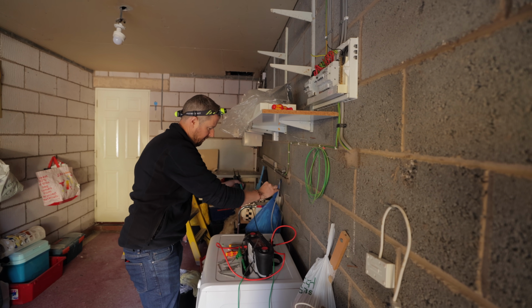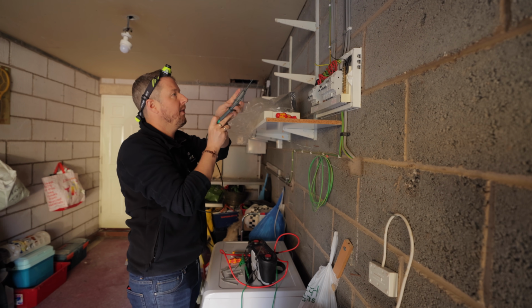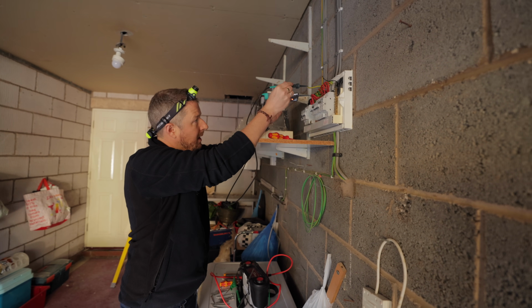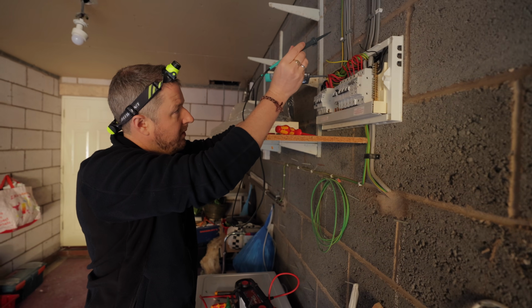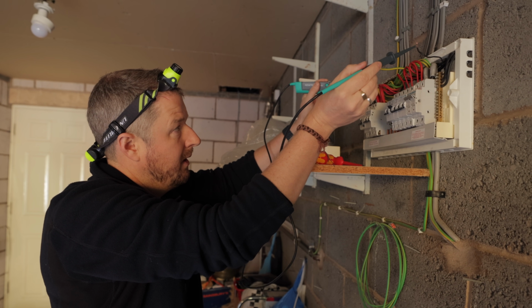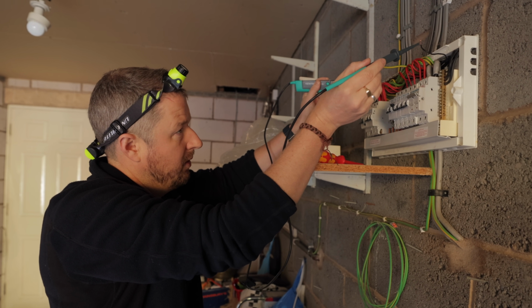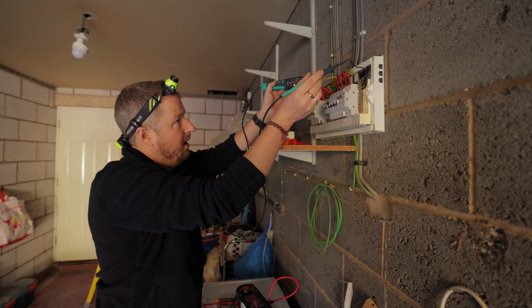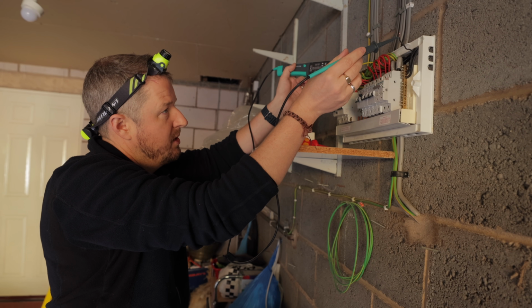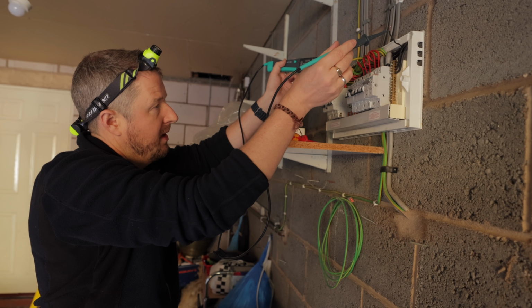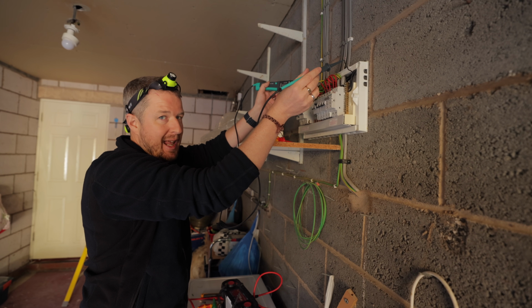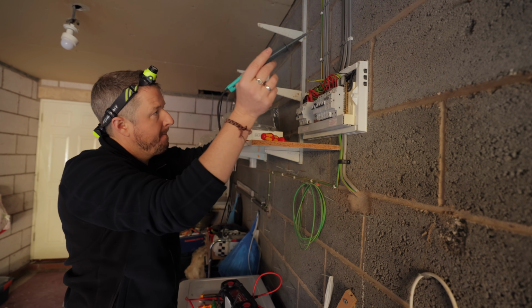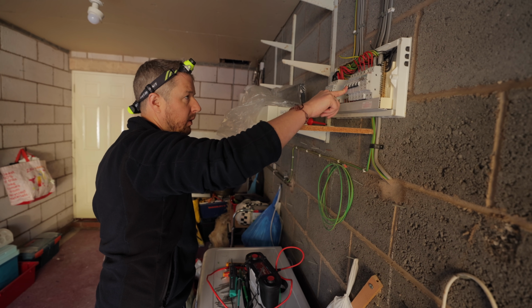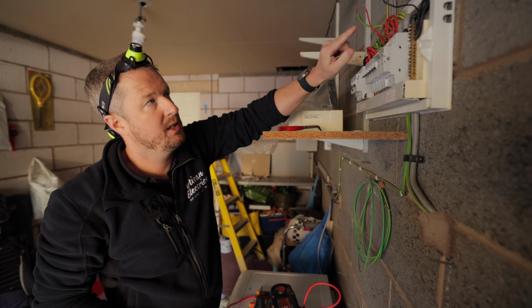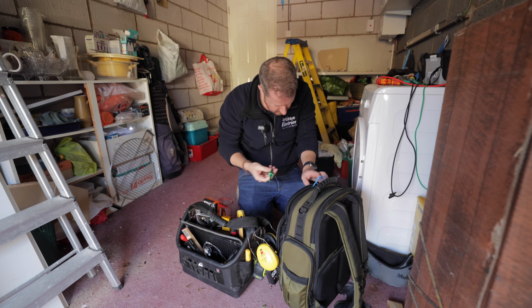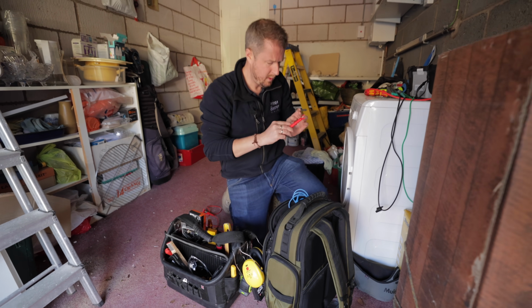Let's see what voltage we've got on the earth compared to true earth. Okay, we've got 50 volts, not normal. And there we've got 120 volts. We've got nothing between neutral and earth. There might be some kind of weird neutral earth fault, but only when the circuit's turned on, which might indicate a polarity issue. So now what we're going to have to do is what we call an R1 and R2 test. We're going to check every light fitting to see whether the live and neutral, or the line and neutral, are the right way round or not.